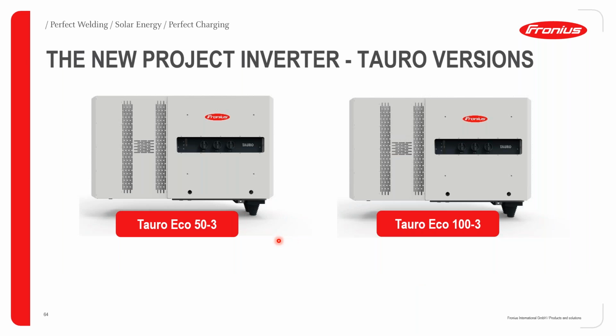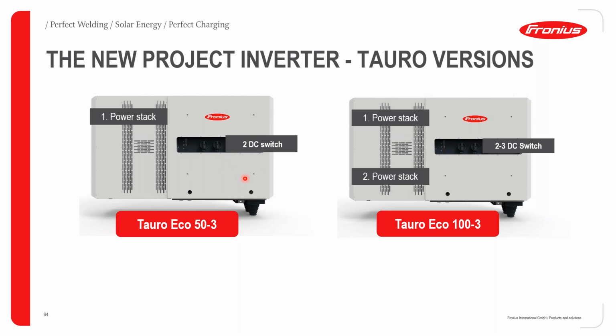So let's look at a bit more specific details about the two inverters, the 50 kilowatt and the 100 kilowatt inverter Tauros. As you can see here, the construction of the inverter is slightly different, as I have mentioned. This is the area that is containing the power stack. And then the 50 kilowatt inverter has two DC switches, so you have two possibilities whereby you can switch off your DC power independently.